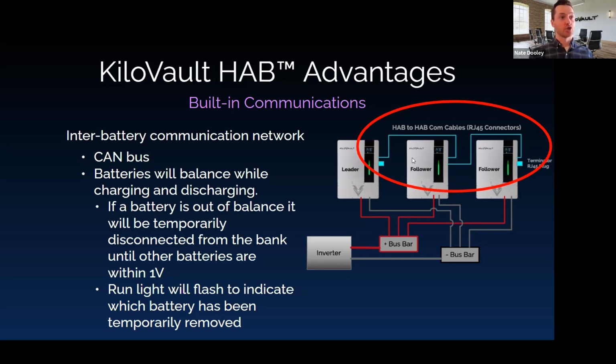Let's say battery 2 is 2 volts higher than batteries 1 and 3. What will happen is you'll actually notice the green run light will be flashing upon charging, and what that means is that this battery has pretty much removed itself from the parallel connection of batteries, and is going to stop accepting a charge until the other batteries arrive within roughly 1 volt or so.